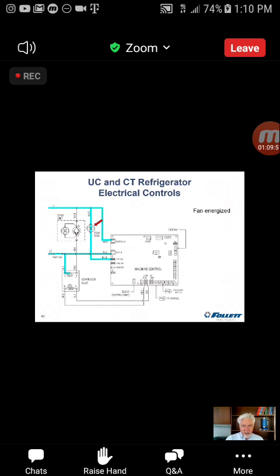The first thing the board does is it energizes the evaporator fan motor. On countertop refrigerators, it runs continuously, all right? It never turns off. On under-counter refrigerators, it cycles with the compressor. So when the compressor is running, it's running. When it's off, that fan will be off as well.